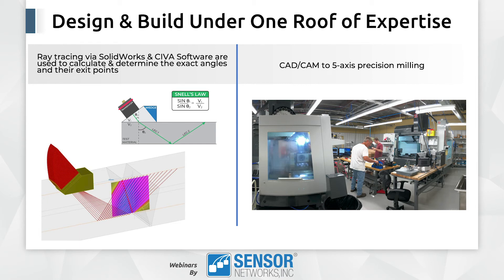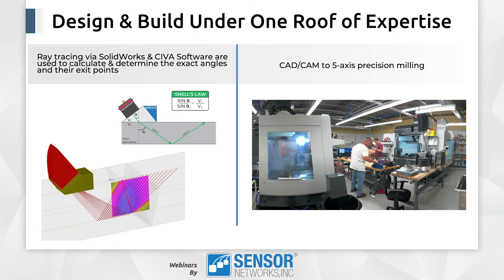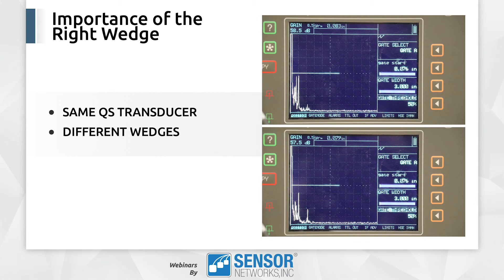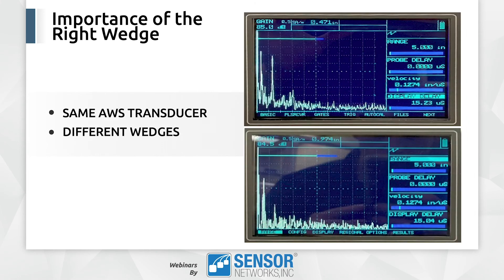Probably the biggest thing we do at Sensor Networks is that we are very vertically integrated when it comes to wedge manufacturing. All the design and all the manufacturing are done here in the facility under one roof. We use SolidWorks and CIVA to do the design and modeling of complex wedges, both mechanically and acoustically, and we use 5-axis CNC CAD-CAM milling machines to produce those wedges. Through our latest design of both mechanical and acoustic damping materials, on average we've been able to achieve anywhere from 3 to 6 dB better signal-to-noise ratio than our competitors. The next two slides will show our quick-change wedge design for angle beam inspection and our AWS wedge for weld inspection compared to our competitors.